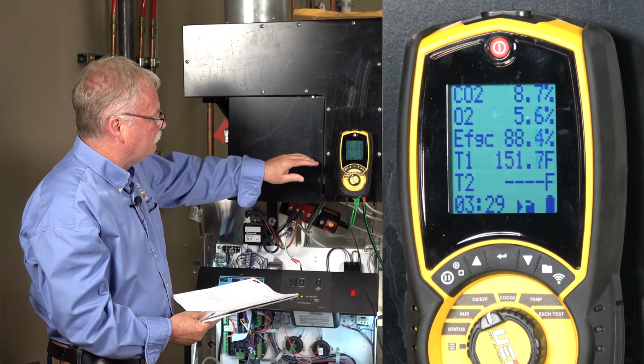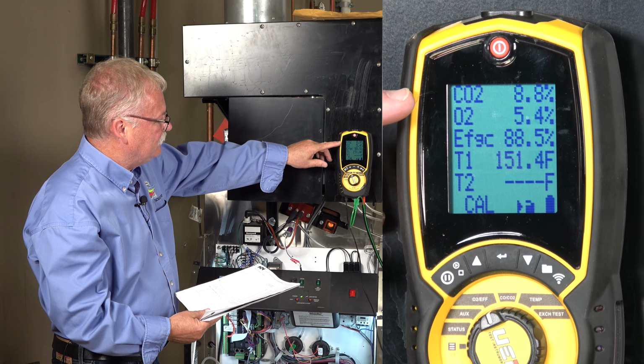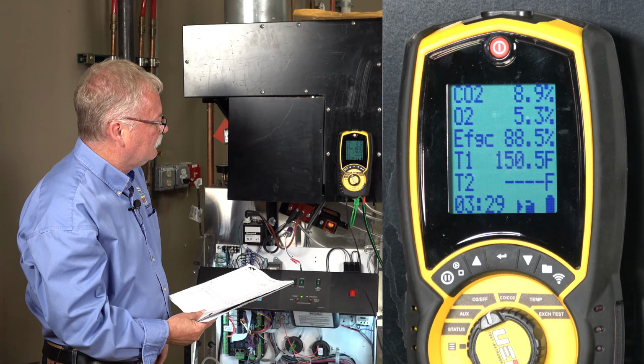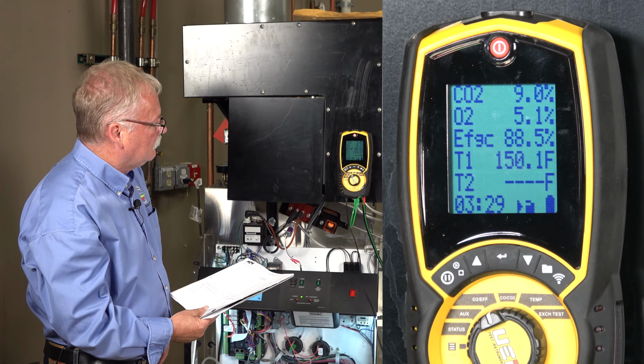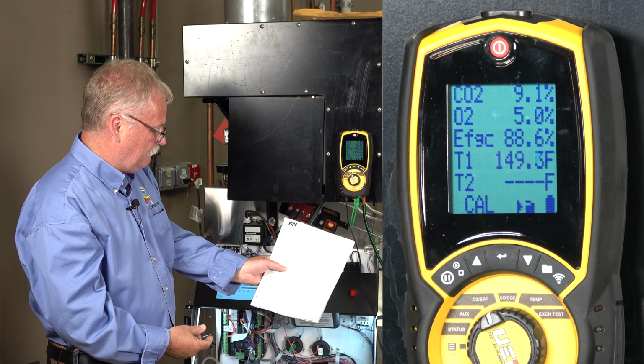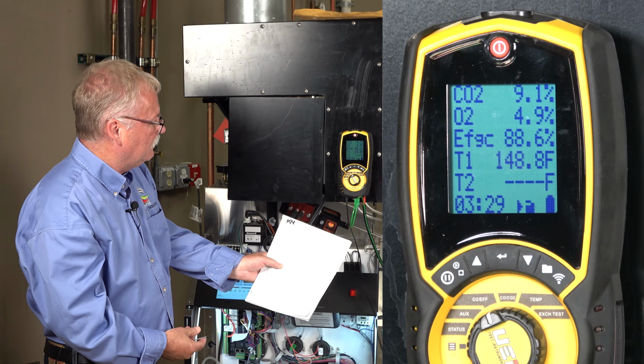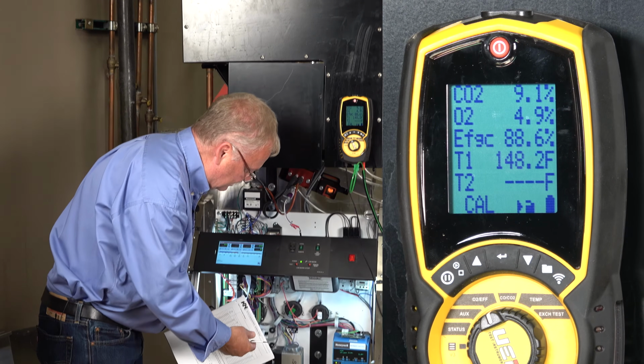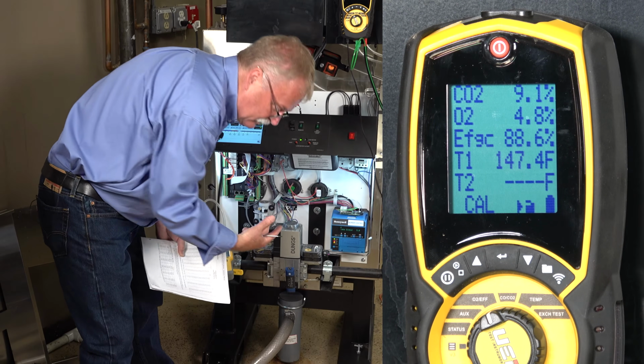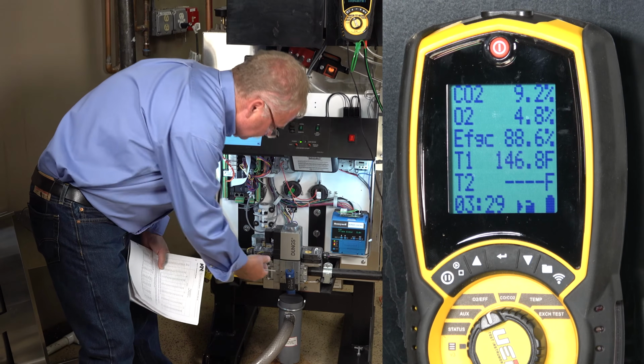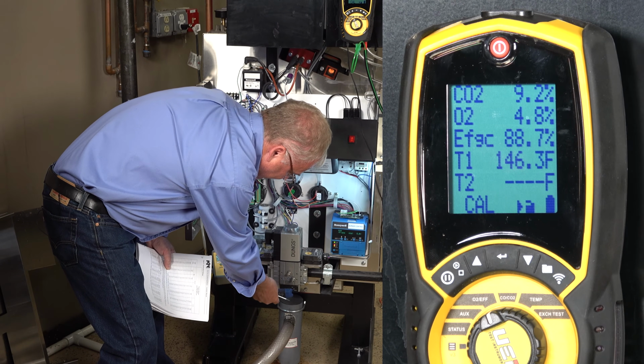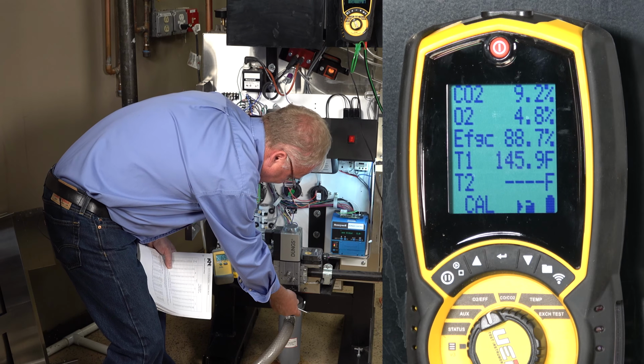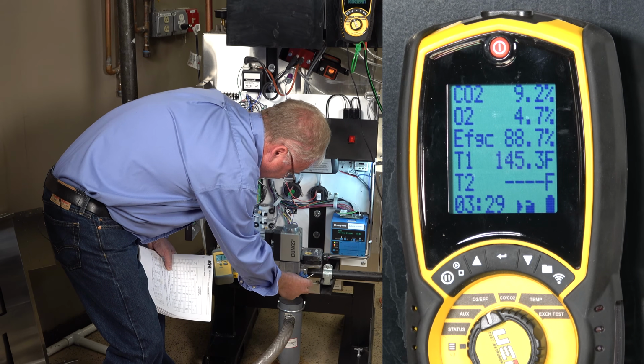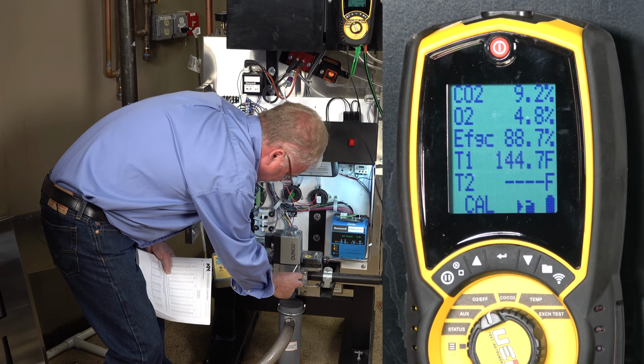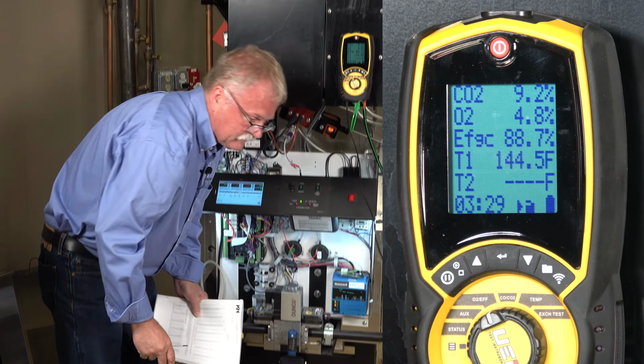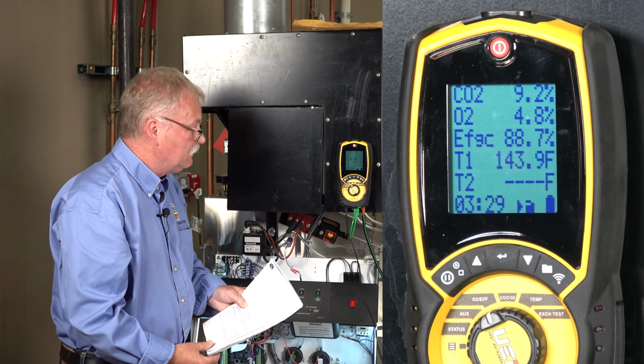My temperature is pretty much stabilized. My CO2 is going up a little bit. I said it should be in the 8.4, 8.5 range. It's actually going up. So that means I want to go the opposite way. I've given it about 15, 20 seconds. So I'm going to take my half turn back. And I'm going to go half a turn off there. As you can hear, it quieted up.